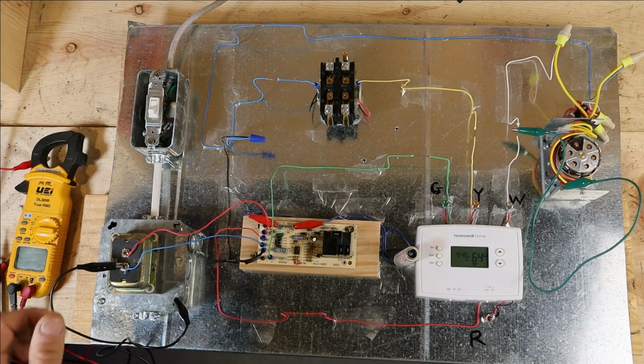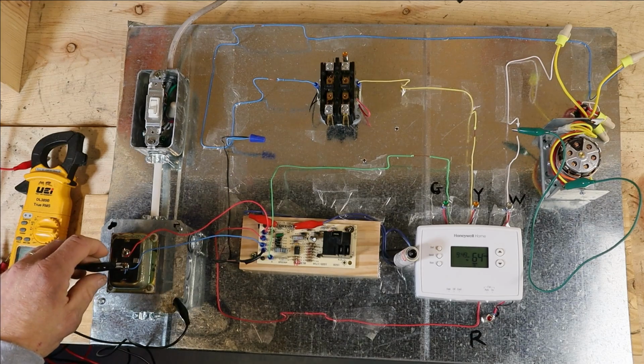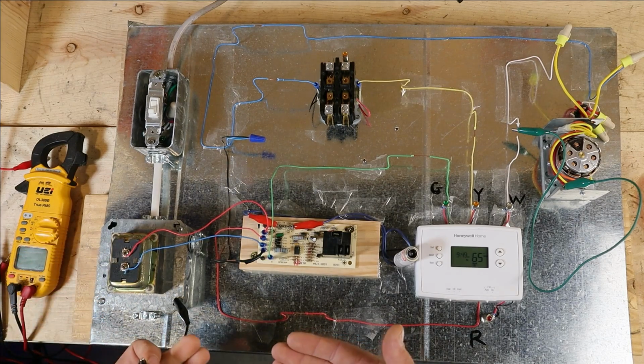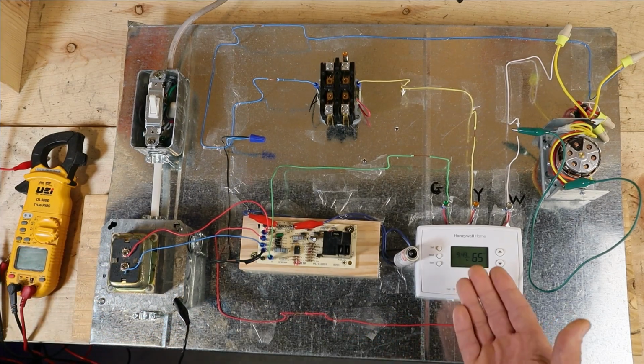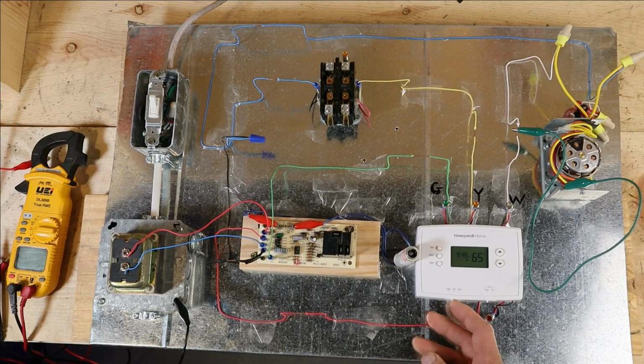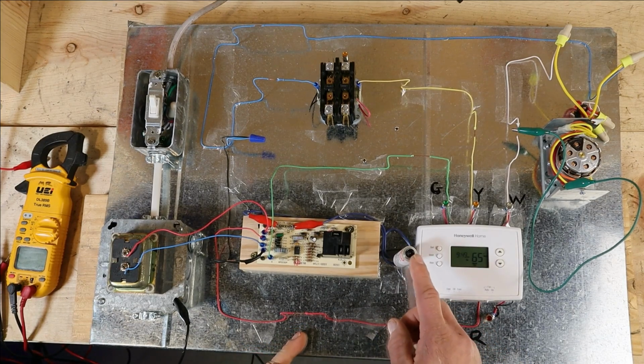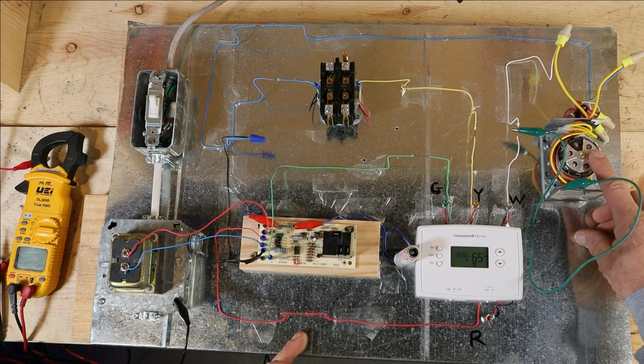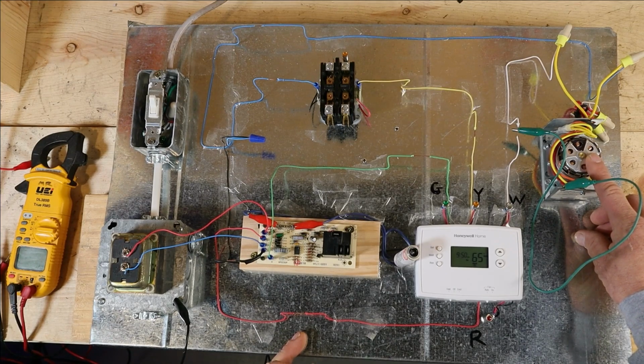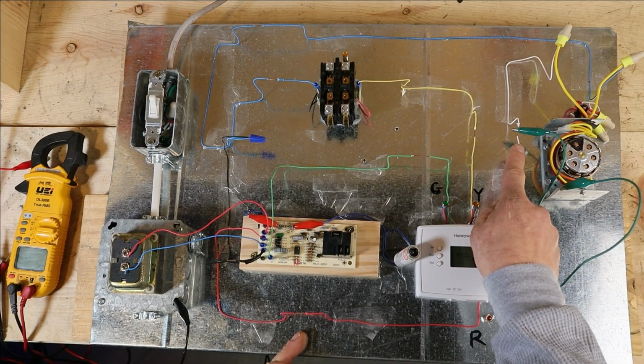So what I'm going to do now is remove the grounding of this secondary and turn it into a floating circuit. I'm going to turn my thermostat back into heat mode, and you can see we do not have a blown fuse. So what this is telling me is that my zone valve motor is still providing the resistance this circuit needs to prevent a fuse from being blown. So now I know I'm looking for a bare wire touching metal.